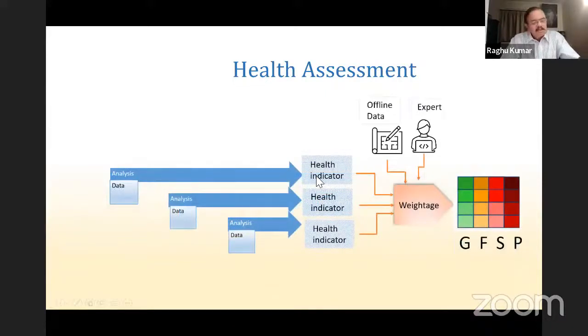This is how this health assessment is calculated. Multiple data are available from the condition monitoring, like your temperature data, your oil data, your loading information, your tripping information. These data give you a health indicator. And then offline data are there, like I told you, electrical tests which are conducted, oil analysis done separately, visual inspections, thermal imaging. All these offline data are also put in. Then there are expert opinions. There is a worldwide knowledge base available, and these experiences are also put into this algorithm. And certain weightages are given for each indicator.